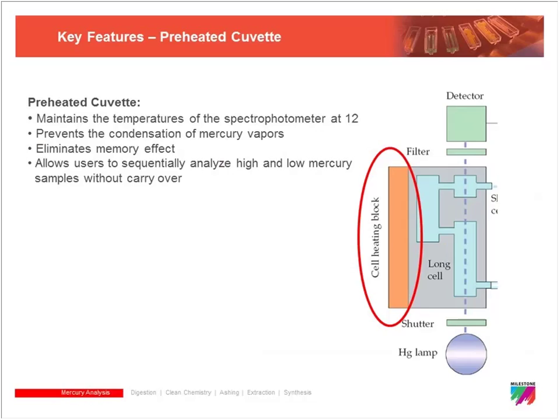As another part of this automated feature, reducing any memory effect or carryover, we keep the spectrophotometer cell preheated. This keeps any mercury species volatilized. The problem in some of the conventional techniques is that mercury can tend to stick around inside the system. This is designed to keep the mercury from sticking inside the detector cell, so that further reduces and nearly eliminates any memory effect you have from higher concentration samples to lower concentration samples, by keeping the mercury completely flushed through the system.